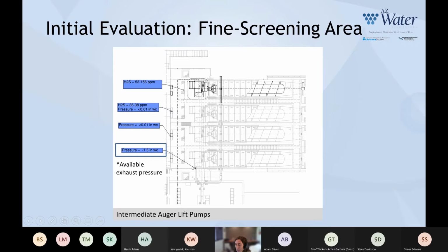The available static pressure in that duct was negative 1.5 inches of water column. So what that was telling us was that there was available suction pressure, but it's basically like sucking through a straw with a bunch of holes in it. There wasn't enough suction to get all of that foul air out. So instead, due to the pressurization tendency of the screw pumps, you were seeing migration coming out of those channels.